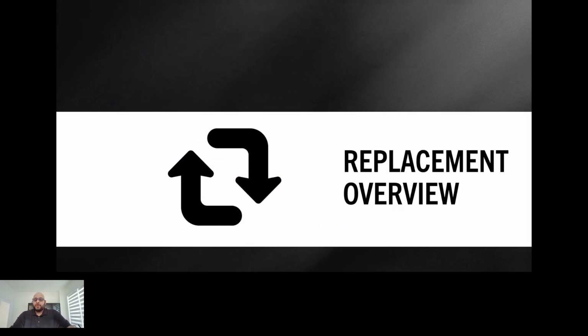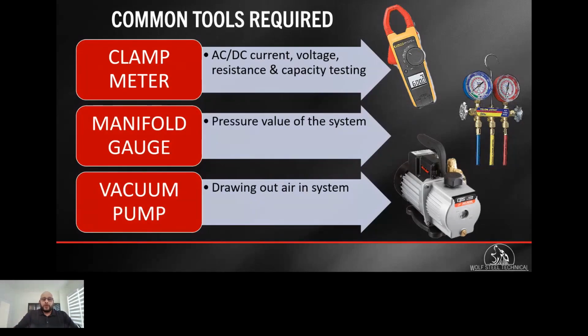So, replacement overview. Let's discuss what's required to replace the equipment. Some common tools are your multimeter, your manifold, and your vacuum pump. Some of the things that you might need are a flush kit and a flaring tool, and these are very specific to the installation process. As a technician, you should know how to use your tools to calculate your subcooling and your superheat in order to charge the system properly.